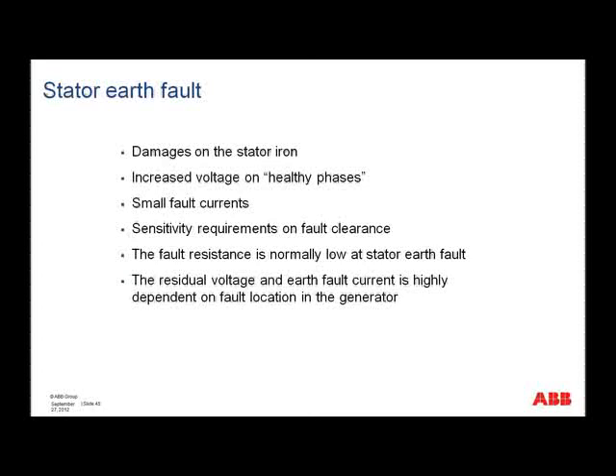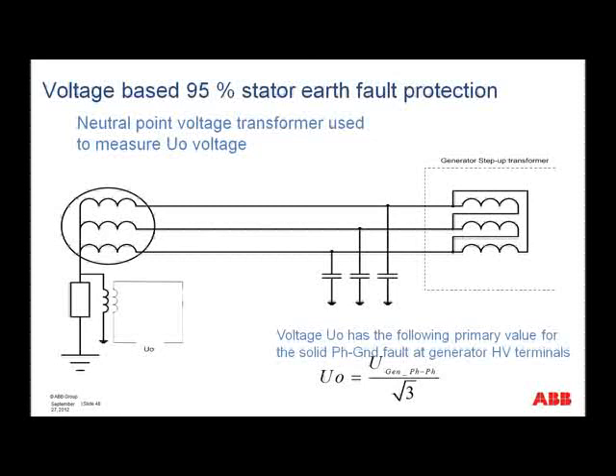Because of the small fault currents, we have a reasonably high sensitivity requirement for the fault detection. The fault resistance is normally low at stator earth fault, because the fault, I guess, is to the core. And then the residual voltage and the earth fault current are highly dependent on the fault location in the generator, and that you will see from these next pictures. Now, here they're showing measuring the stator earth fault voltage based, and if the fault were here on the terminal, then in primary value, the value of U0 primary would be given by this.